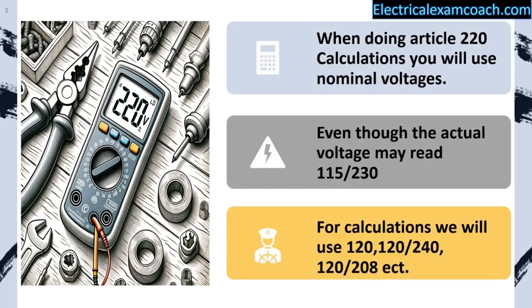When doing Article 220 load calculations, we're going to be using nominal voltages. Although our actual meter reading might be 115 or 230, for our calculations we're going to use nominal system voltages like 120, 240, or 120/208. It makes it a lot easier, not having to guess what the actual voltage readings might be.